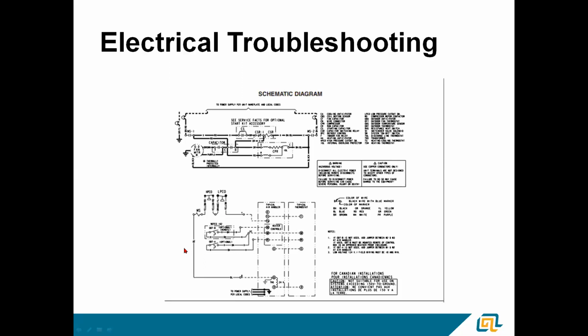Down here in the 24 volt, what I wanted to show you is that this system actually has a high pressure and a low pressure control. They are in series. So you've got your Y1 coming in, it runs through the high pressure control, runs through the low pressure control, and hits the MS, which is your motor starter or your contactor.